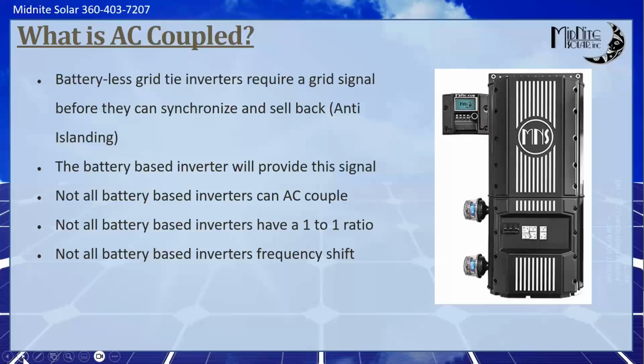And as the last bullet point says, not all battery-based inverters frequency shift, and not all of them do it in a logical or intuitive way, that's what I'm looking for. It's not always intuitive how you would do that. Like on a Magnum PAE, for example, you have to put it in custom battery mode in order for it to frequency shift. The Rosie, you have to enable AC coupling, and I think like the Schneider products, you also had to enable AC coupling to get frequency shift.